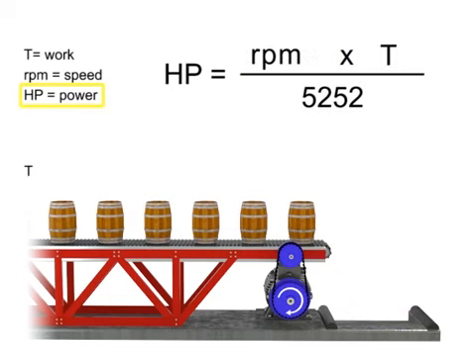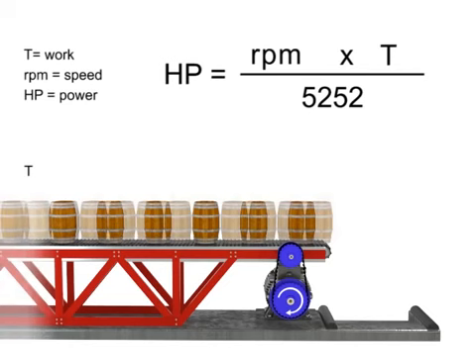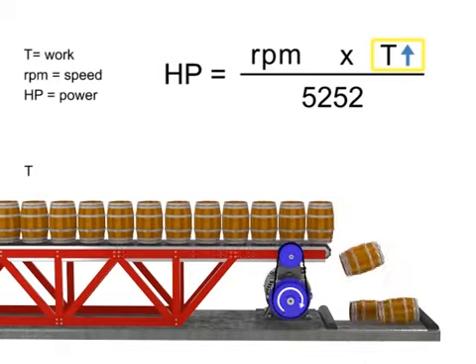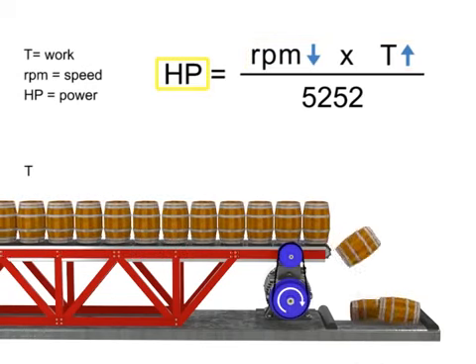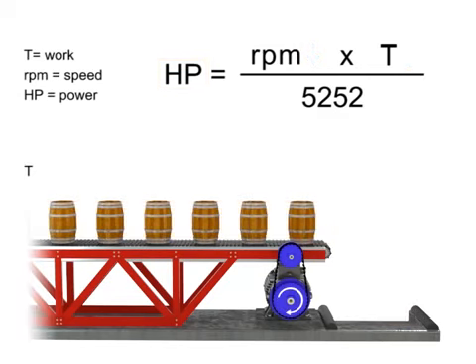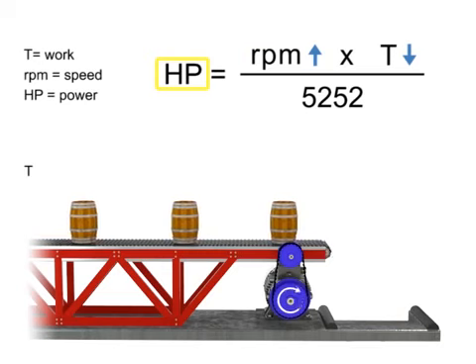If horsepower remains constant, then speed and torque are inversely proportional. As the torque increases, speed decreases to maintain constant horsepower. As torque decreases, speed must increase to maintain constant horsepower. Let's say we want the horsepower of our motor to remain constant, but wish to increase the torque. If torque increases, the speed of the conveyor decreases so that the horsepower required of the motor remains constant. If the torque decreases, the speed of the conveyor increases and the horsepower remains constant.